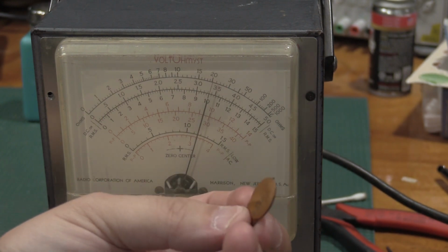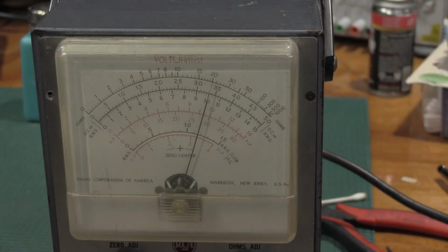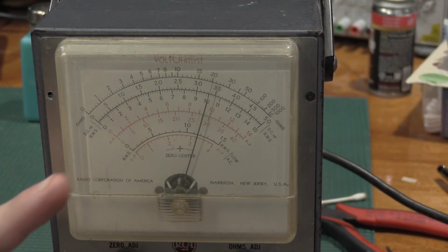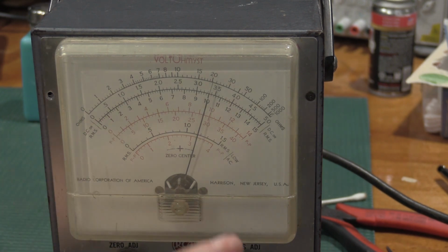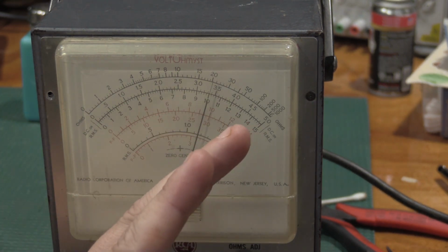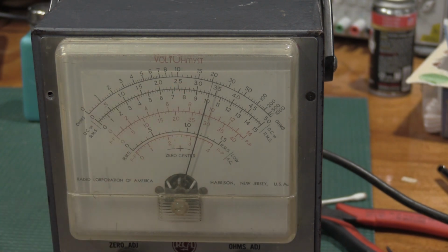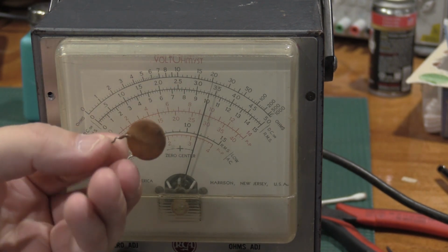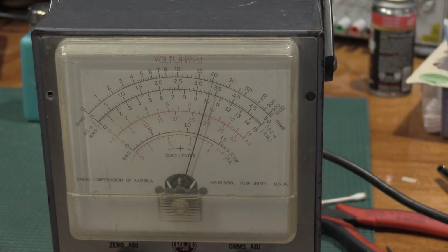this capacitor. Ceramic caps typically don't go bad, but this, for whatever reason, floated out of value and was very lightly coupled, which also explains why when the meter was cold, it would be overvalued, but then when it warmed up, it would fall back. So, and this is one of the critical caps in the AC line, but doesn't affect the DC. So I'm going to double check the DC, but then if the DC is fine, should be good to go.